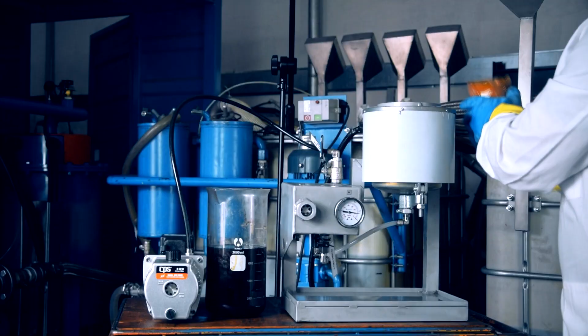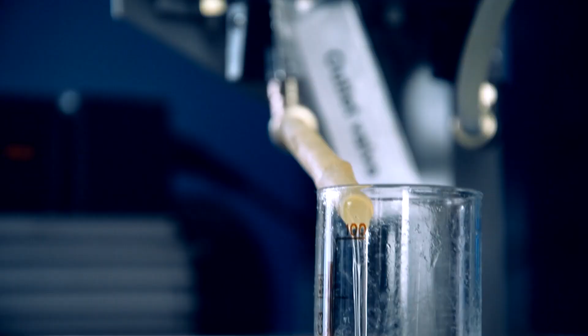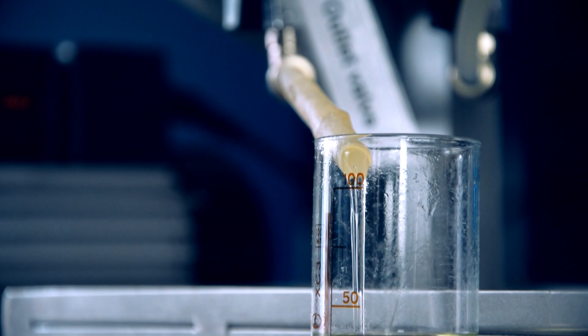One of the advantages of the regeneration unit is the use of Fuller's Earth sorbent, which can be reactivated many times. This gives the unit the capability to process oil continuously without stops to change saturated sorbent.